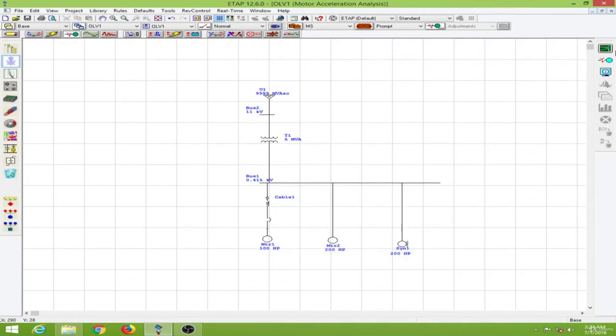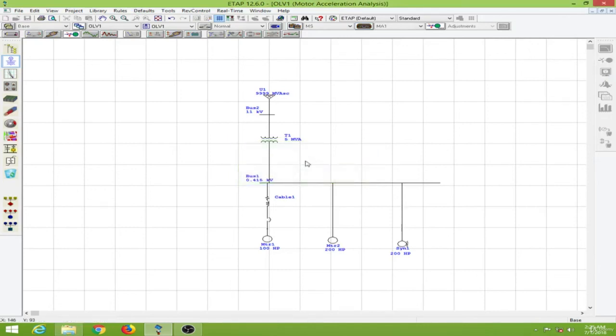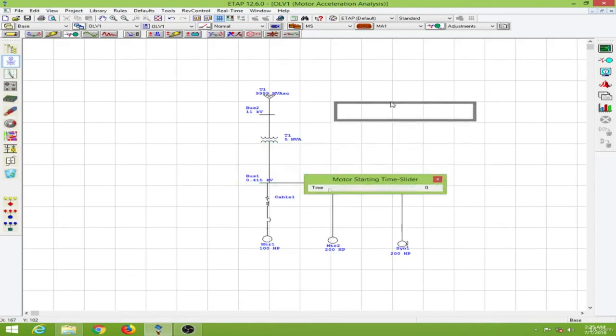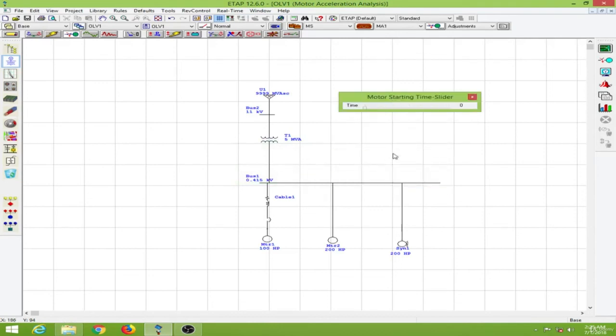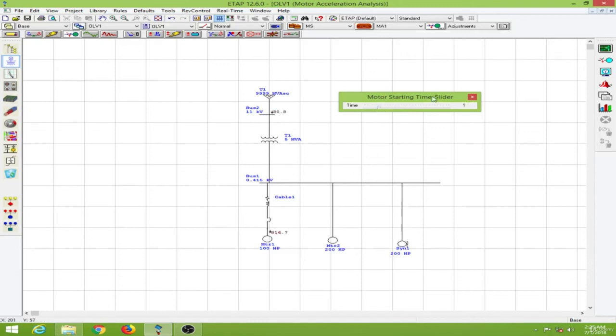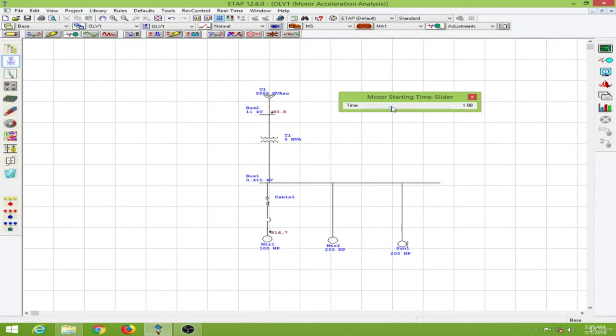And let's run the static motor analysis. So static motor starting analysis I will go over here and click on this. So let me put a file output. And now we have the motor starting time slider over here. So let me move this time slider to 1 second over here. So at the first second you can see the motor 1 has been started and we have the load current for the motor 1. And as you go over here at 2 seconds you can see this motor has been started.